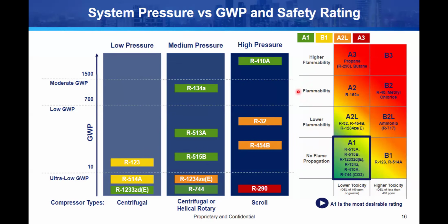Then we had 1, 2, and 3 to indicate how flammable it was. 1 means what I would call non-flammable, but technically it's no flame propagation. It is flammable because you can burn those things. You can burn R410A, right? You can burn R22. It's just that when you take your torch away from it, it goes out on its own. It doesn't keep burning. It won't propagate the flame. So it's basically non-flammable. So that would be A1s. A2 would be flammable, and A3 would be highly flammable, like propane, right? Or butane, which we are fully aware burns, right?